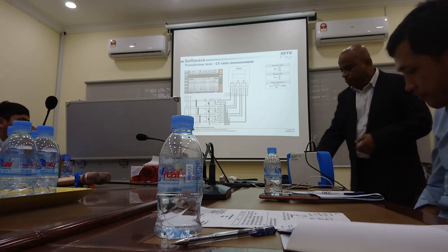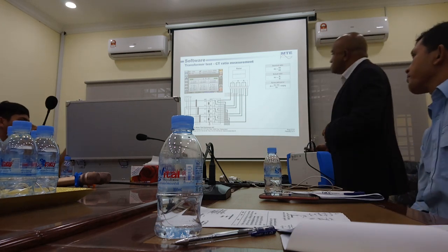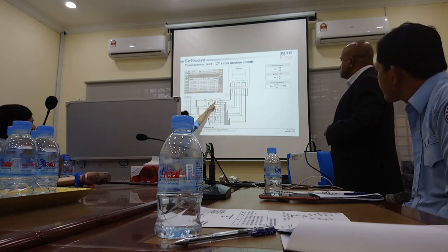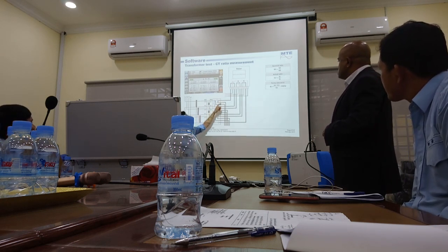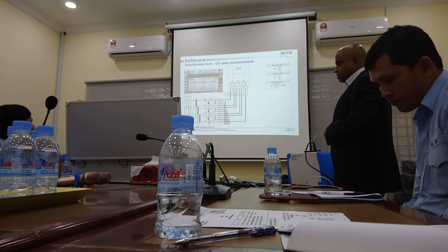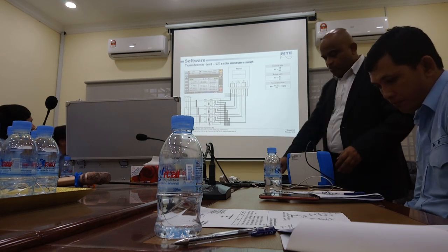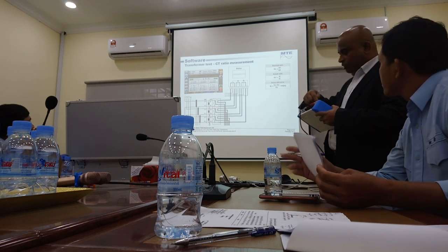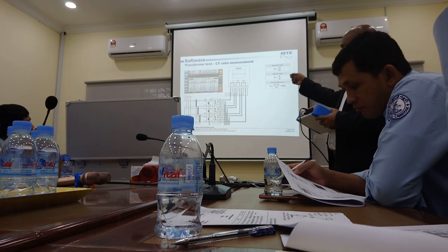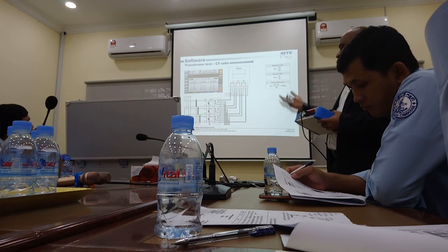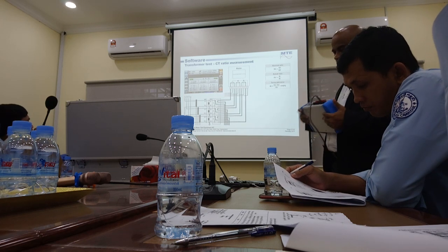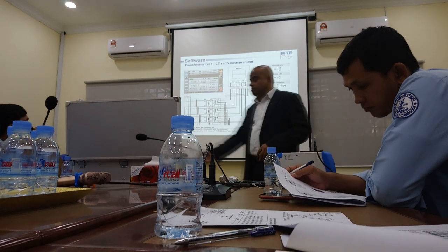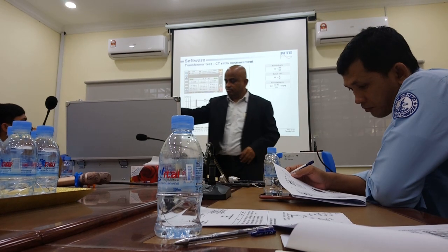Why this diagram here? You need to scroll down, not directly here. Good question. In this diagram, it is using these wires, not a clamp. It is going through the meter and coming back, because it is a CT secondary, so it is 5 amps. You asked a good question, so let me explain that.